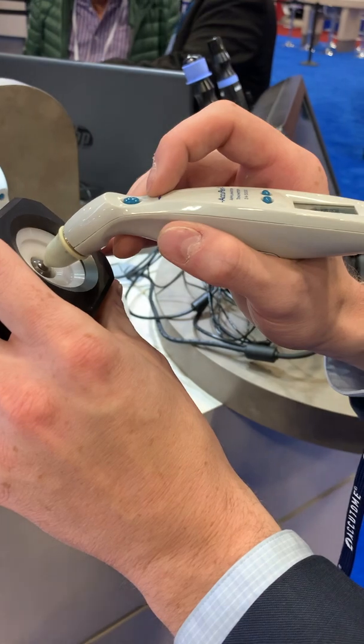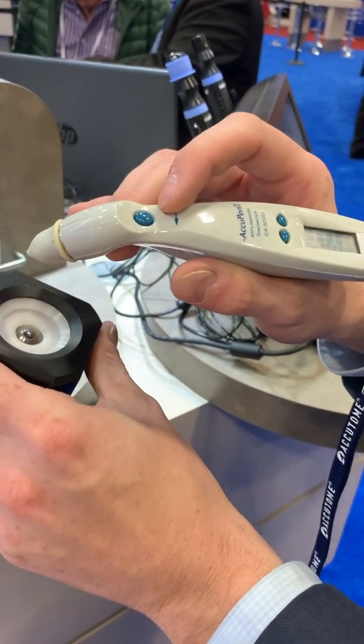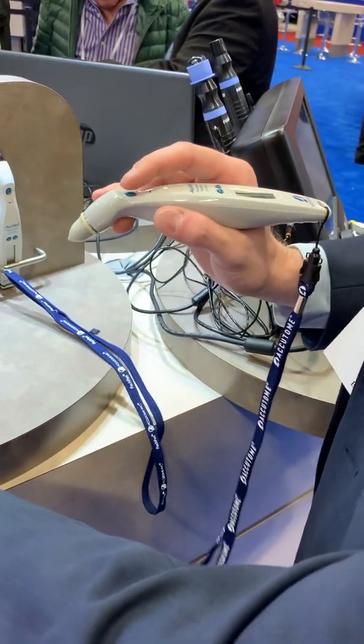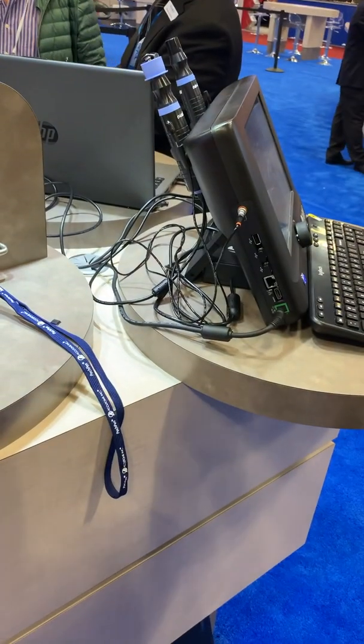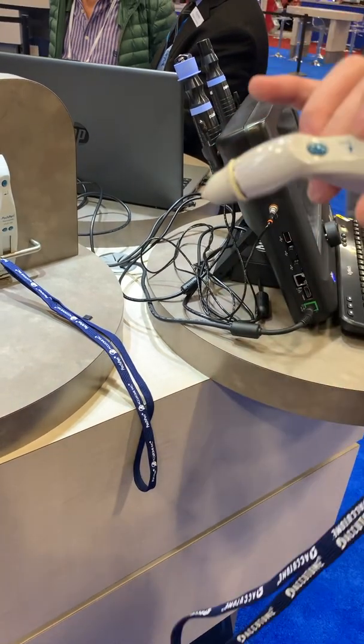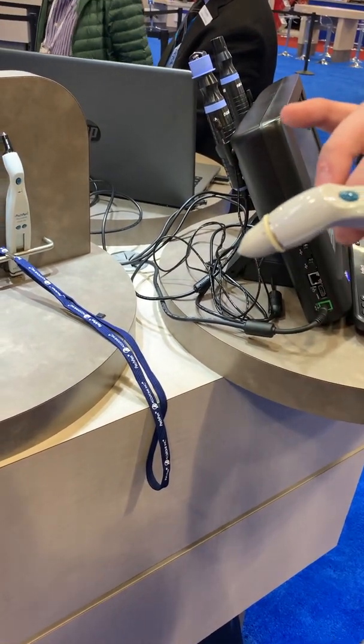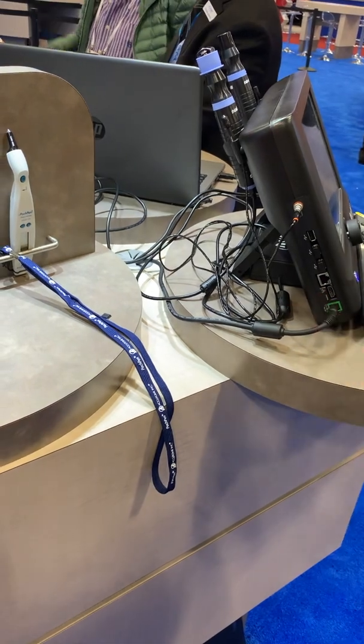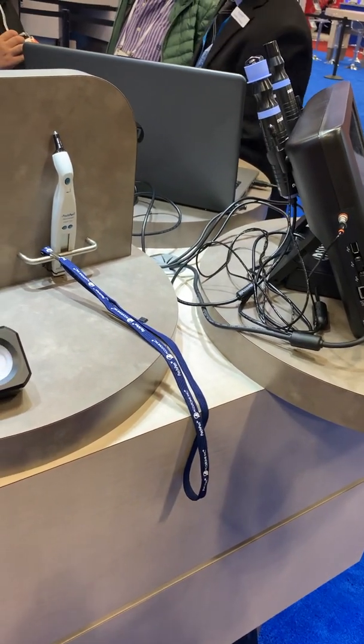So how many times do you press the cornea? What it's doing is every tap is taking a small measurement. And we're not confident in that measurement until we've gotten a few measurements. If two pair together match, then it's going to give us a reading. And I can take up to 9 of those readings, 9 readings per eye. So we have to press 9 times per eye. Yep, you're going to do it a few times.